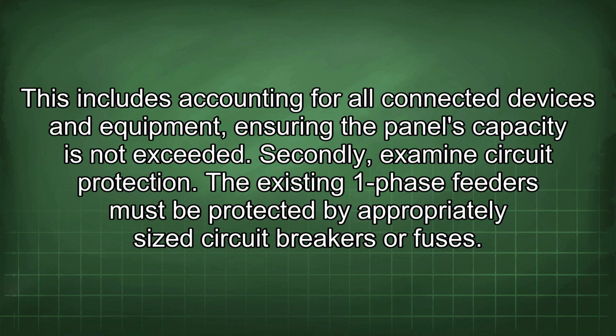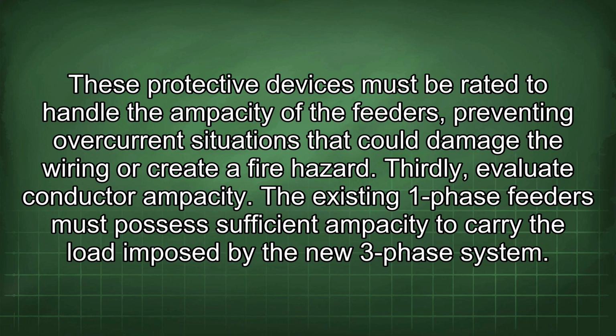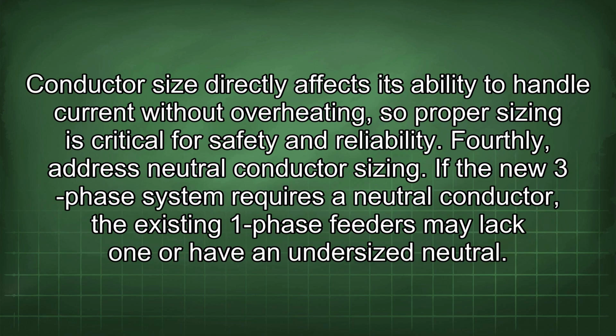Secondly, examine circuit protection. The existing one-phase feeders must be protected by appropriately sized circuit breakers or fuses. These protective devices must be rated to handle the ampacity of the feeders, preventing overcurrent situations that could damage the wiring or create a fire hazard. Thirdly, evaluate conductor ampacity. The existing one-phase feeders must possess sufficient ampacity to carry the load imposed by the new three-phase system. Conductor size directly affects its ability to handle current without overheating, so proper sizing is critical for safety and reliability.